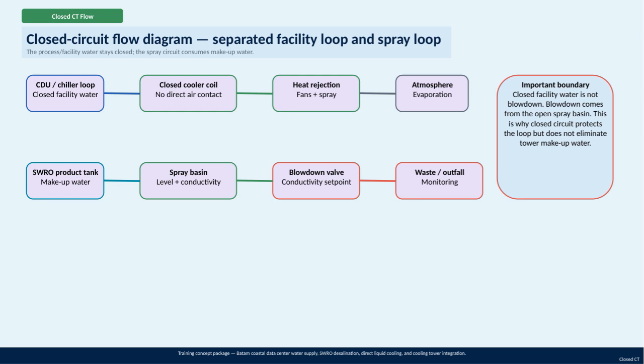Specifically, the closed-circuit chiller loop circulates water within the facility without any direct air contact, protecting the quality of the water and maintaining cooling efficiency. Heat rejection happens in the closed cooler coil via fans and sprays, where evaporation to the atmosphere takes place in the spray basin. Makeup water flows into the system from the SWRO product tank to compensate for what evaporates, while the spray basin level and conductivity are carefully monitored.